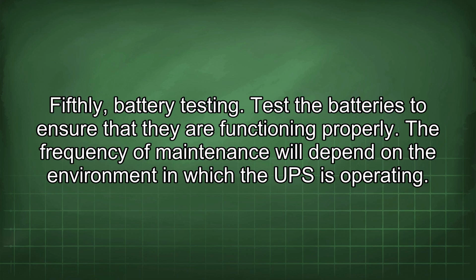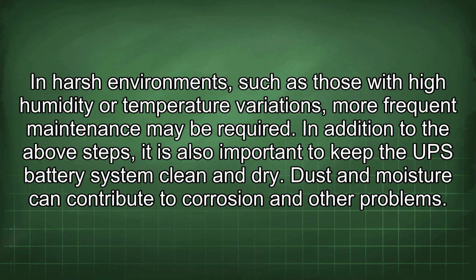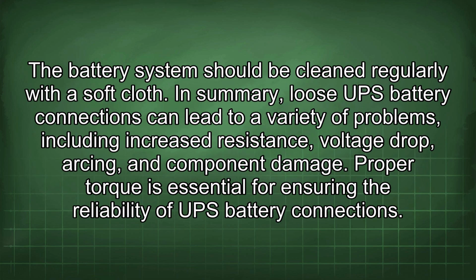Frequency of maintenance will depend on the environment in which the UPS is operating. In harsh environments, such as those with high humidity or temperature variations, more frequent maintenance may be required. In addition to the above steps, it is also important to keep the UPS battery system clean and dry. Dust and moisture can contribute to corrosion and other problems. The battery system should be cleaned regularly with a soft cloth.